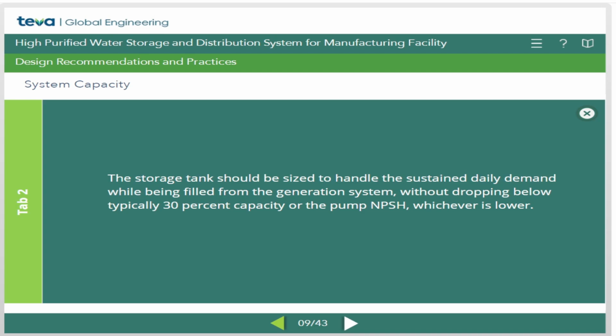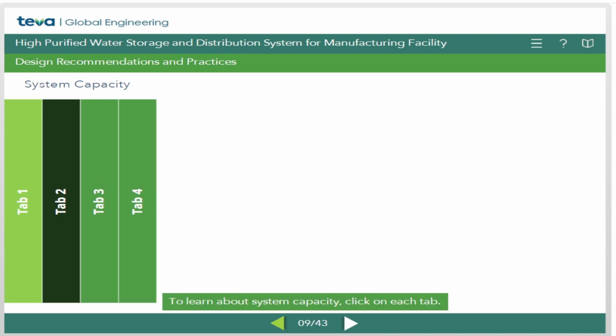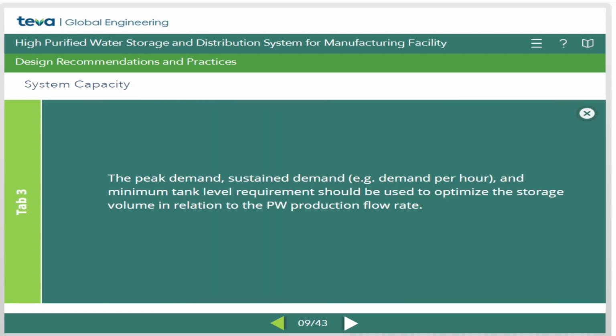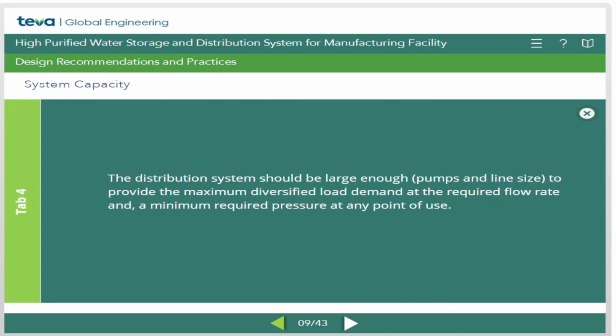dropping below typically 30% capacity or the pump NPSH, whichever is lower. The peak demand, sustained demand, and minimum tank level requirement should be used to optimize the storage volume in relation to the PW production flow rate. The distribution system should be large enough to provide the maximum diversified load demand at the required flow rate and a minimum required pressure at any point of use.